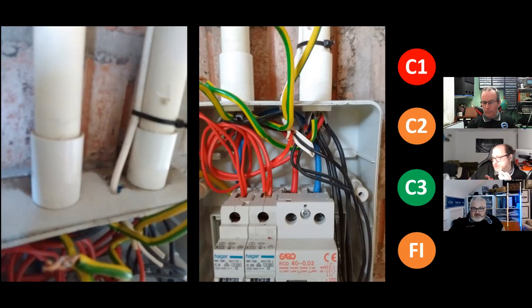You can see they've put a Garo RCD with Hager stuff. They've got at least three cables in it. You look at the size of the main tails. It just, to me, immediately screams out there's no good workmanship or materials. This was tested, inspected and sent to me. It was just really bad workmanship and materials all round. Mixture of manufacturers. It was a DIY job for anybody who asks. And it seems to be a lot of multiple circuits into breakers these days. Well, yeah, it saves the end user a fortune, doesn't it? They don't get subdivision of installation.